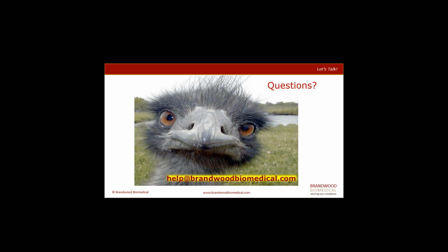Question from Romit Sin. Is prototyping considered part of design control? To some extent, depending on Romit, yes. Some forms of prototyping may be required to undertake, for example, some clinical evaluation. So prototyping is very much part of design control.